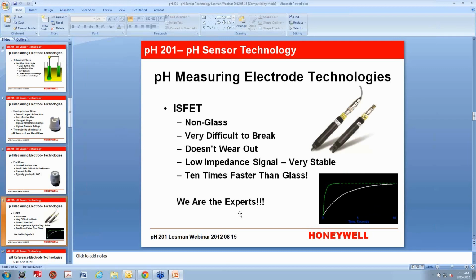Okay, so our last pH measuring electrode technology is the ISFET. ISFET stands for Ion Sensitive Field Effect Transistor. It's a little piece of electronics put into a little plastic body, and has some layers in it so that it's protected, and then it's all melted and heat sealed. It's non-glass, which is wonderful because you can put it in the process and it won't break. It's unlikely that you would break it during a calibration. In fact, sometimes you can even drop it on the floor and it doesn't break, which is pretty nice.